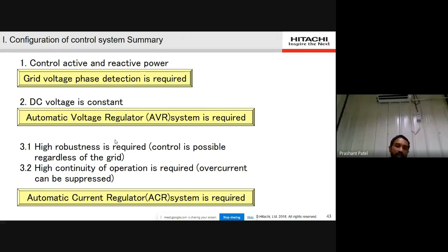Now we will see about the phase detection method. The phase detection method is used for the synchronization of your converter with the grid. Conventionally, normally everyone is using PLL based synchronization control. We are just measuring the grid voltage. There is a phase signal detection unit. It generates sine omega t and cos omega t. So sine omega t is exactly in synchronism with your U phase voltage, which means R phase voltage. So normally there are two familiar methods, like the PLL based method.